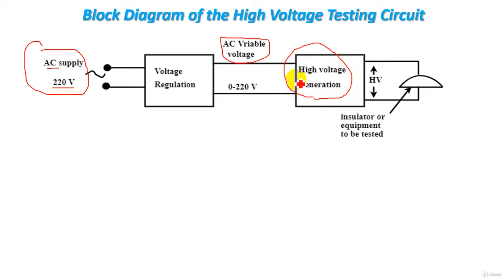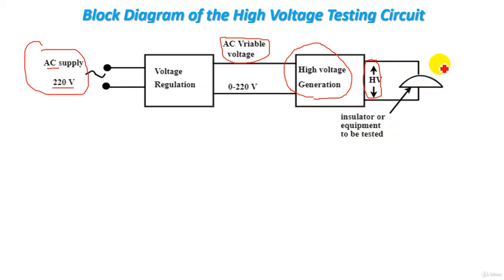The high voltage generation stage is used to produce a high voltage. This high voltage is applied to the insulator, specimen, or equipment to be tested, in order to determine the breakdown voltage and dielectric strength of the insulator and ensure its proper operation in the electric power system. This is the simple block diagram of the high voltage testing circuit.